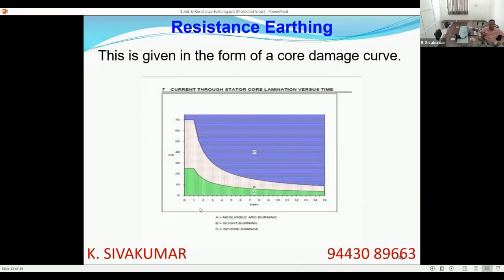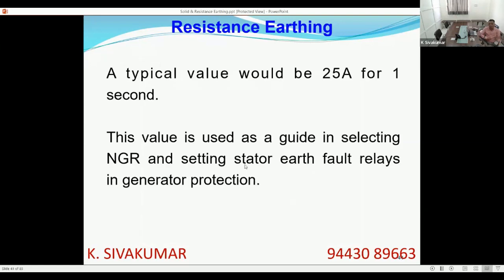This is the green zone, so negligible burning is seen. So generally this is 20, this is 30, this is 25 ampere for 1 second. So generally 25 ampere for 1 second is the core damage limiting value. This is used as the guideline in selecting NGR and setting up the stator earth fault relays in generator protection schemes.